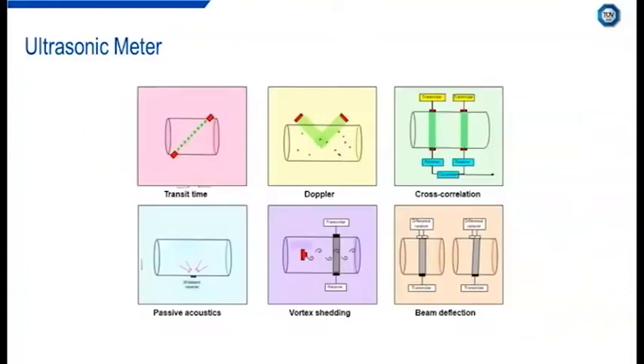Our last example of our modern types of single-phase metering available is the ultrasonic meter. Ultrasonic meters use sound waves to determine the velocity of a fluid flowing in a pipe. At no flow conditions, the frequency of an ultrasonic wave transmitted into a pipe and its reflections from the fluid are the same. At flowing conditions, the frequency of the reflected wave is different due to what is known as the Doppler effect. The difference in frequencies transmitted and received are proportional to the fluid velocity.